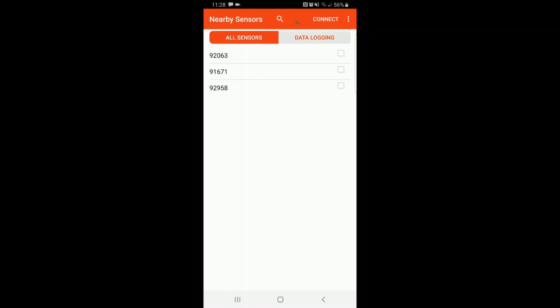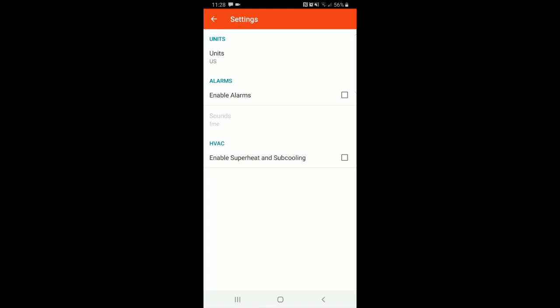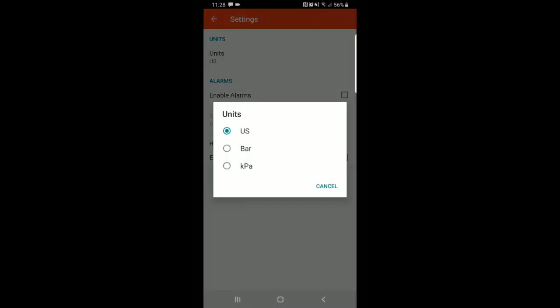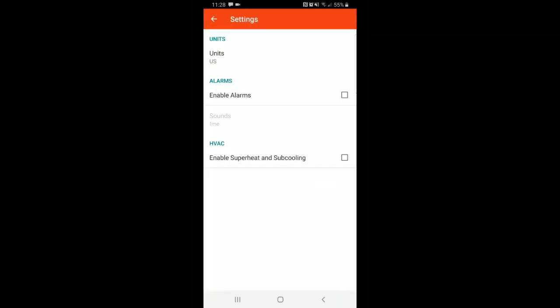Prior to making the selection of the transducer in which you would like to use, there are available options to you that must be set. By selecting the Options tab in the top right-hand corner, and then selecting Settings. Underneath the settings, you have the availability to change it into 3 different units of measurement. US is going to display in PSI. You also have the options for bar and kPa. We are going to be using US, pounds per square inch. And through this window, you can also enable or disable any alarms. The high and low alarm setting will be set in each individual transducer screen.